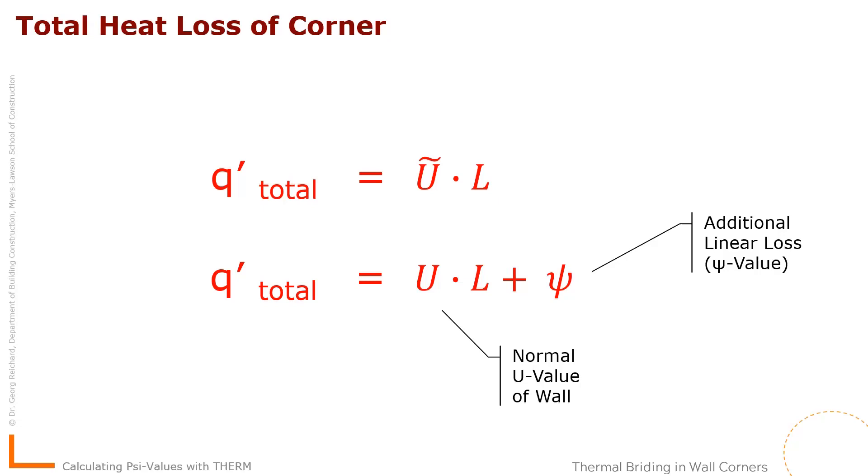So we see here we have two different totals and they are equal. So setting them against each other as equal, we can now then go ahead and isolate for Psi, which exactly shows what we explained before, that the Psi value is the difference between the average U value over this total length minus the simple U value. So basically just adding Psi to the simple solution will give us the total loss.